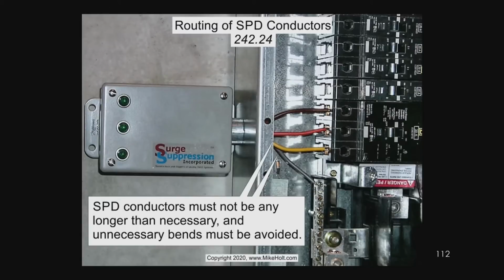All right, let me do a final closing here. Surge protection devices are designed to shunt the circuit in a way that it creates a high current circuit, and that's going to drop the voltage down, and it's unrelated in any way with the equipment grounding conductor, and it's not related in any way with the ground of the surface of a building.